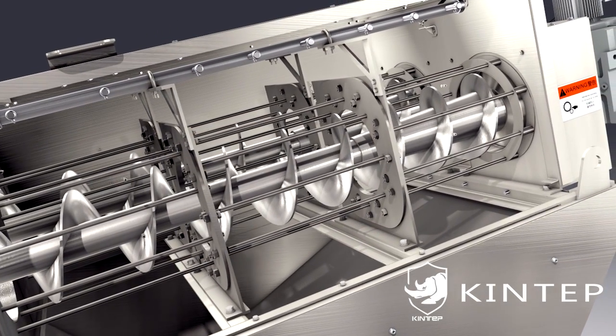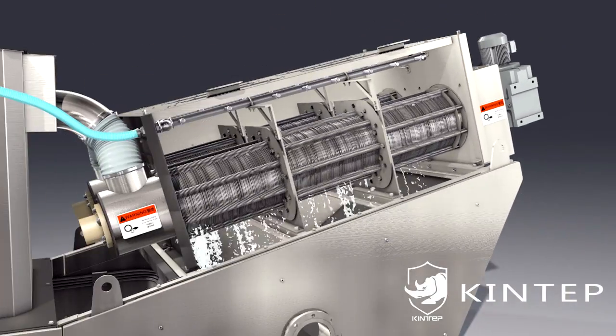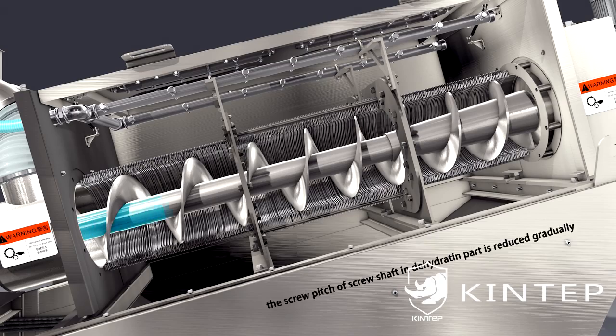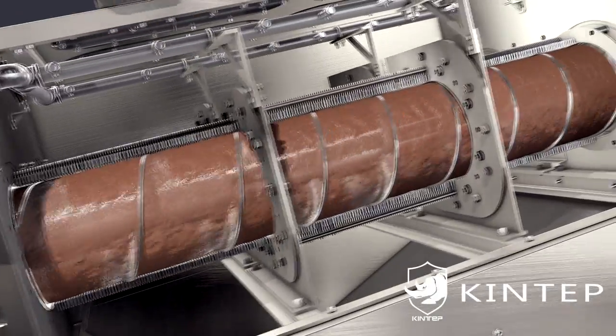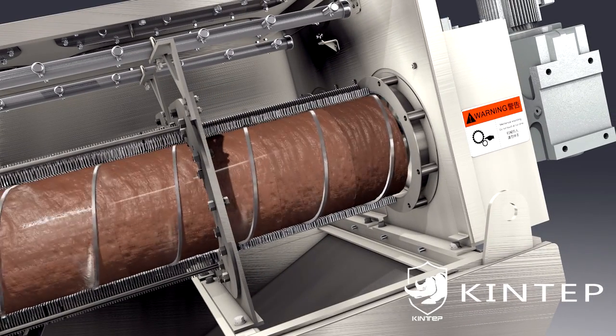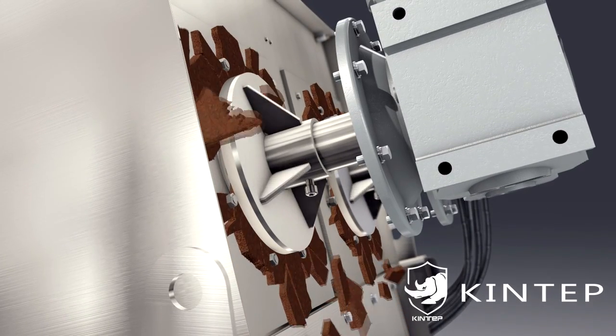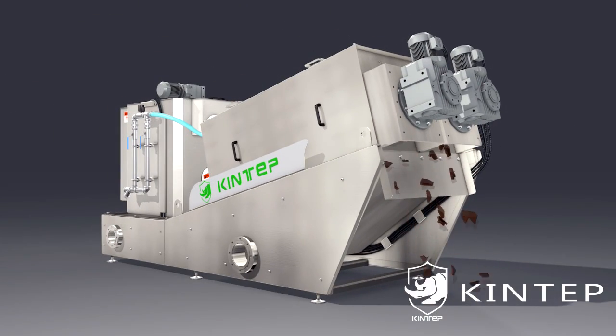The fixed and moving rings move up and down relatively when the screw axis rotates. The water filters out from the gap between the relatively moved rings, realizing rapid dewatering. The screw pitch reduces gradually in the dehydration section, and so does the gap between rings. The sludge moves forward continuously, with the spiral cavity volume shrinking and internal pressure increasing with the outlet and back plate. The sludge gets strong compression and finally realizes continuous dehydration.